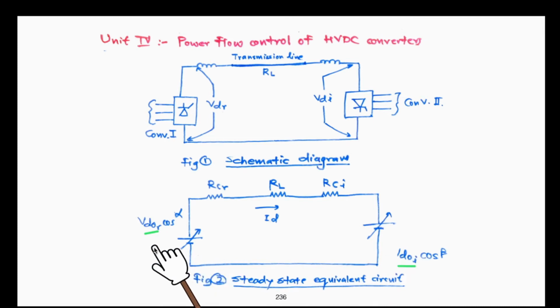They will be decided by the transformer output at the rectifier end. Similarly, they will be decided by the tap ratio at the inverter end, okay. Then the next set of parameters that are deciding the control function of voltages at rectifier inverter end are firing angle and advance angle, which are controlled by the microprocessor, the firing angle control, the firing circuit, okay.